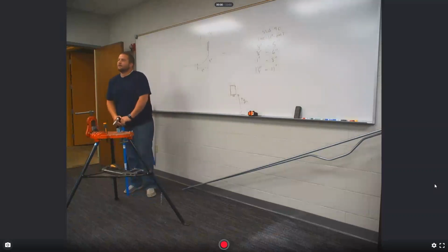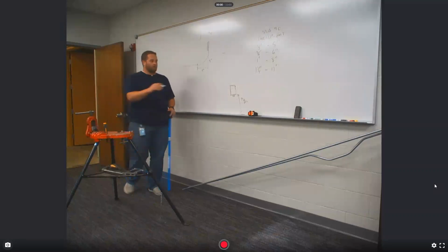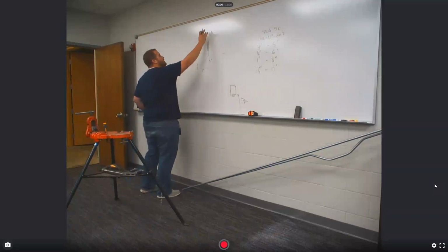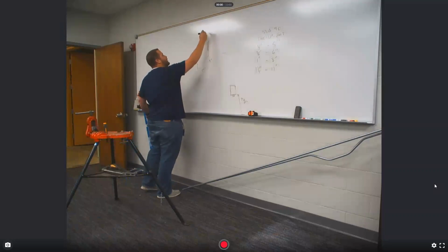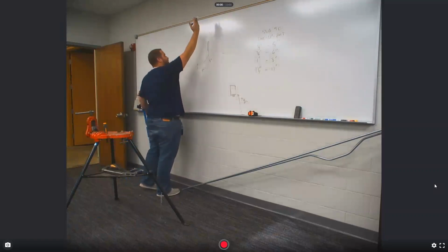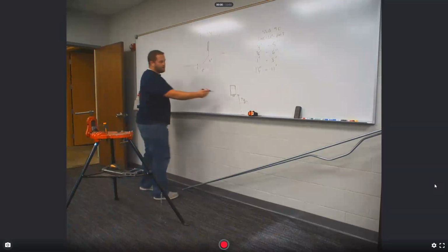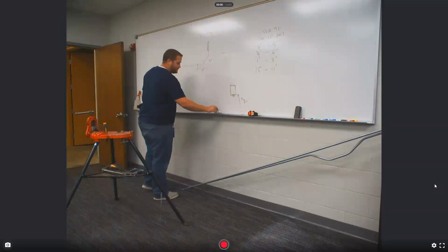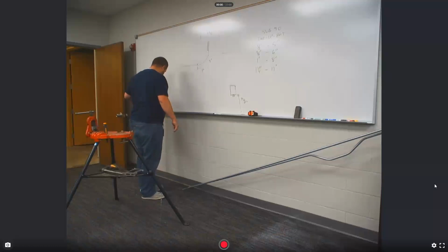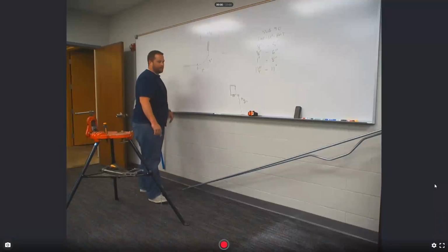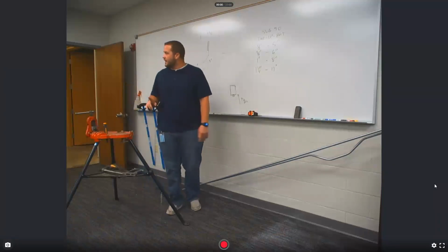4 3/8. Yes, sir. So when I mark my flat piece of pipe, I actually need to mark it at 4 3/8 inches so that when it radiuses up, is that a word, then it will end up right at the bottom of that fitting. And you're thinking, is that really true? It's going to happen? I'm going to tell you, yes, it is going to happen.